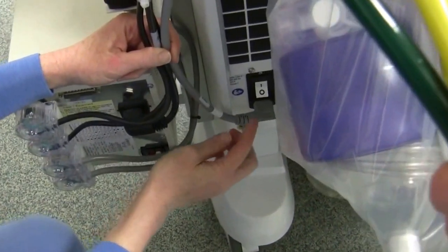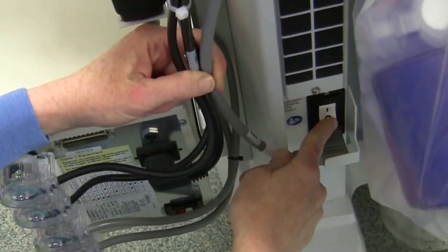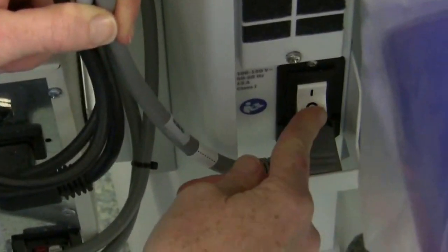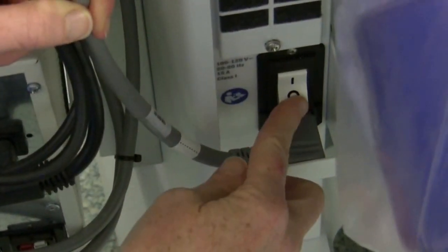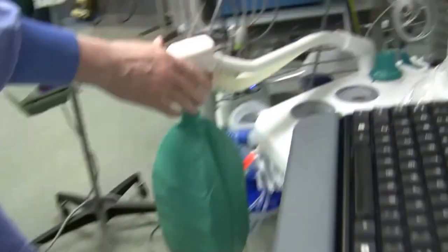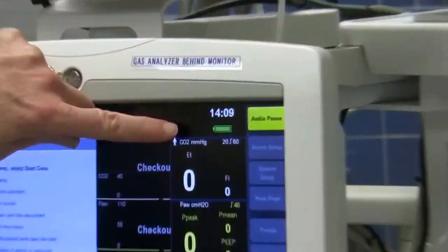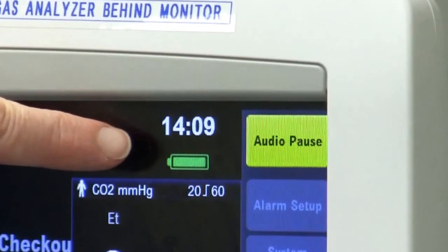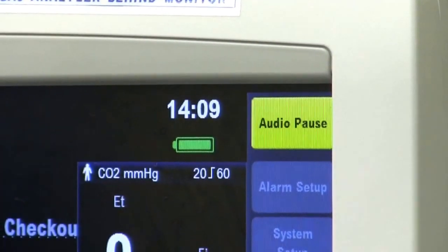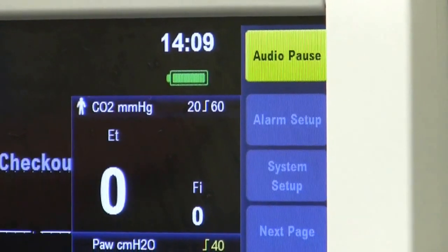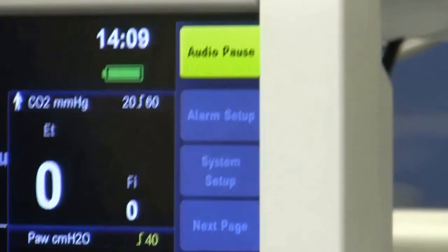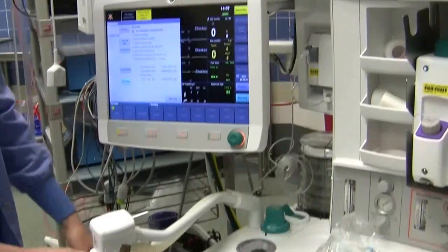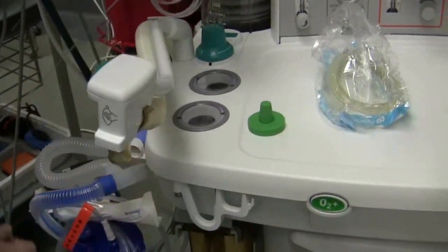So this right here is the fuse box for it. It's the breaker for the machine. It's not necessarily on-off power. So what happens when I shut this off, what I do is I make sure that the battery is full. And here's the symbol for the battery. It's green and full. A full battery lasts about 50 minutes, 30 minutes if you're using a lot of stuff on it. The other thing that I do is I actually check to see if the vent will work on battery.